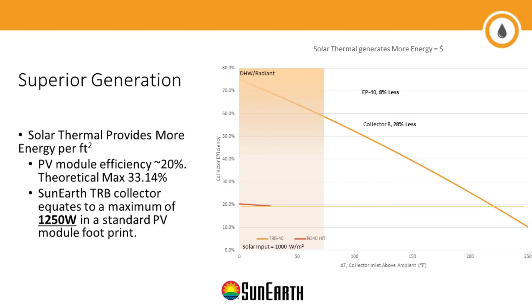But you can see what I've highlighted in orange, up to pretty much 75 or 80 degrees over ambient temperature, that's your domestic water heating and radiant heating sort of spectrum. Within those ranges, solar thermal technology on a per square foot basis is still about 3.5 times more efficient. So if what you need is heat energy and what you have is limited space, which we generally do, working within the confines of something, then solar thermal could be a good choice for your project.